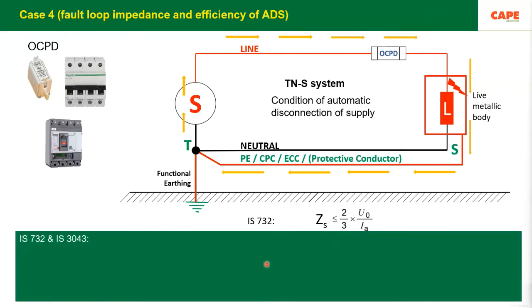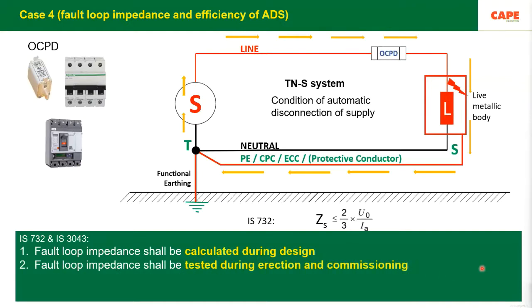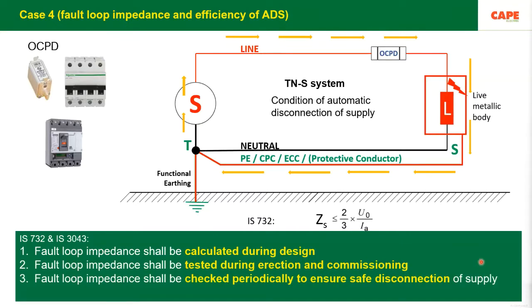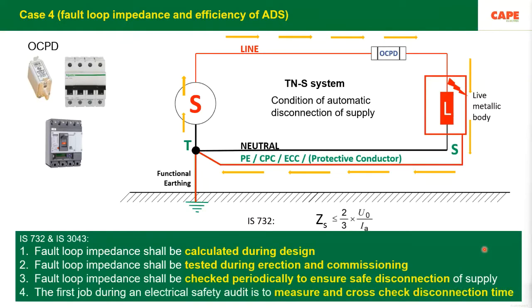Now, the code of practice such as IS 3043 is not a new code of practice. The first standard came, I think, around 1965 or so. The standard has written very clearly that the fault loop impedance shall be calculated during the design. Fault loop impedance shall be tested during erection and commissioning. Fault loop impedance shall be checked periodically to ensure safety of disconnection of supply. And the first job of the electrical safety auditor is to check this particular parameter.